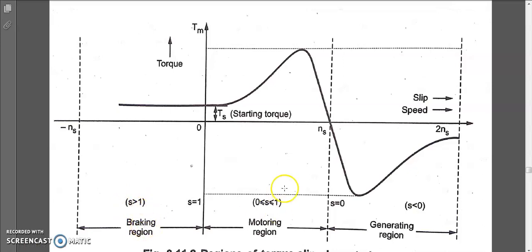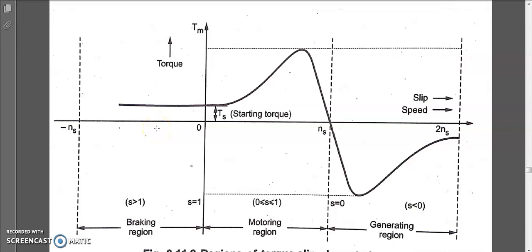In the motoring region slip is between zero and one, whereas in the braking region slip is always greater than one. By interchanging two phases, we change the RMF direction from clockwise to anti-clockwise. The rotor tries to rotate anti-clockwise instead of clockwise, so it decelerates and stops. As soon as it stops, remove the supply connected to the stator.